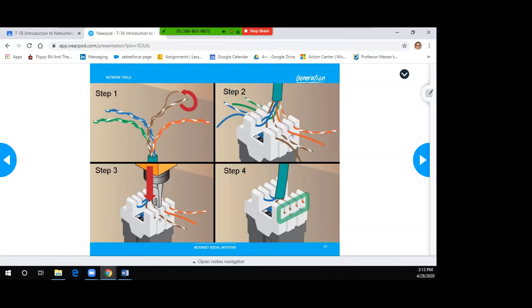One, it gives an appearance of professional work whenever somebody comes and looks at your work. And two, it makes sure that the cable gets bitten once again. When I punch it down, the variance here is that this punch down actually has 2 little teeth, and when you punch it down, it will punch it into place and lock it in, and it kind of peels and bites the cable. So if we don't put this on and we don't make it stay in the bitten portion, it's similar to how the back of your jaw is much tighter than the front of your jaw. It's loose. So then obviously there is no connection.